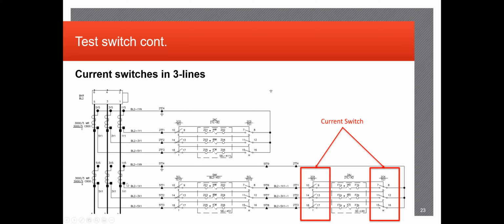So if you reference a point with your meter, and sorry, I'm getting off track a little bit, but you've got to do wiring checks when you're out in the field to verify that everything on the prints matches up. It's fairly simple. We just take a Fluke meter, put it on the ohm setting or the continuity setting, and pretty much just take a reference point and take our other lead and go right down the circuit line to verify that each wire is correctly associated with the point.